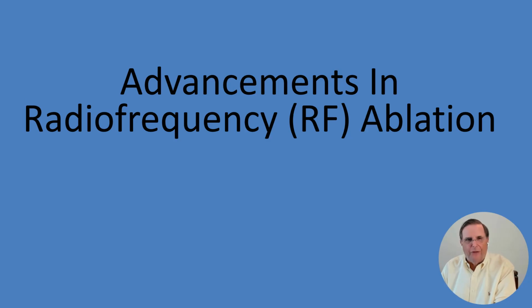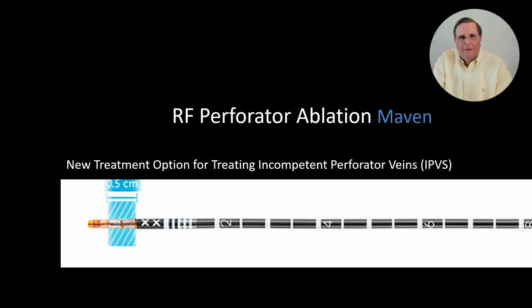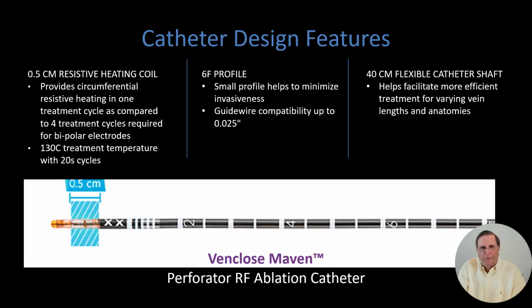So let's look at continued advancement in radiofrequency ablation. Next, I would like to talk about the new RF perforator ablation device called the Maven. It's a new treatment option for treating incompetent perforator veins. It has a 0.5 centimeter resistive heating coil, which is different than the Venclose, being 10 centimeters or 2.5 centimeters. It also has an inert tip being approximately 3 millimeters. The interesting part of this is that it heats to 130 degrees centigrade with 20-second cycles. The catheter is flexible and 6 French and accommodates a 0.025 wire.